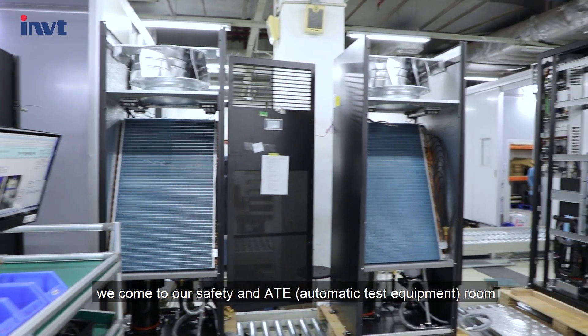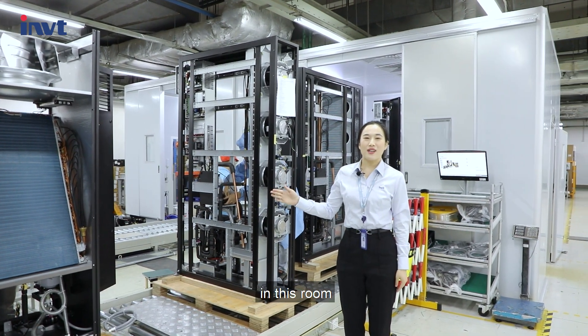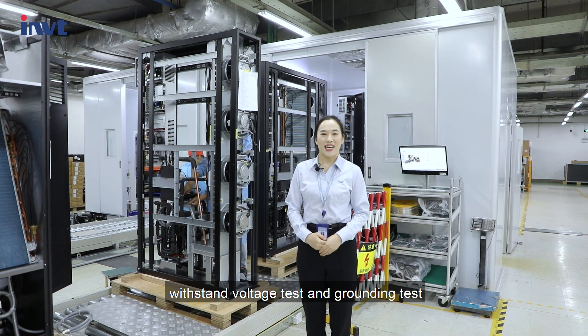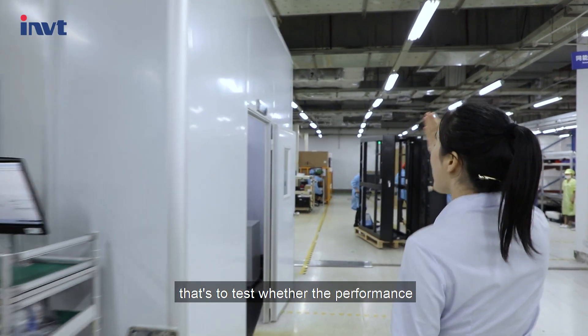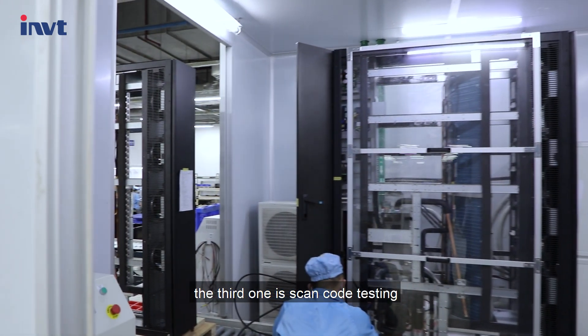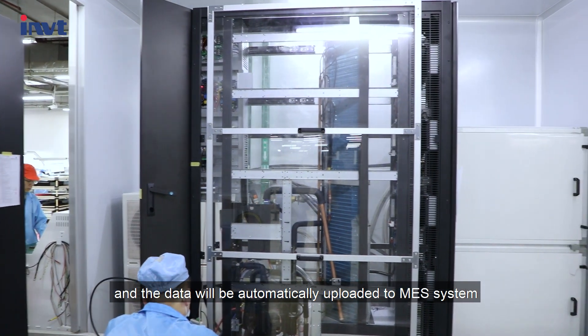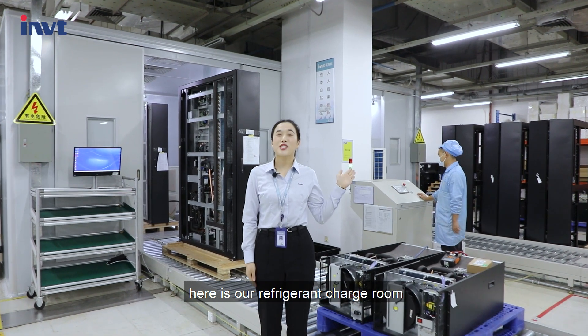Now we have come to our safety and ATE — Automatic Test Equipment Room. In this room we will do three tests. The first is safety testing, including insulation tests, withstand voltage tests, and grounding tests. The second is performance testing, to verify that the product performance meets factory standards. The third is appearance testing. Each product is scanned and the data is automatically uploaded to the MES system. If the product passes, it can be packaged and stored.